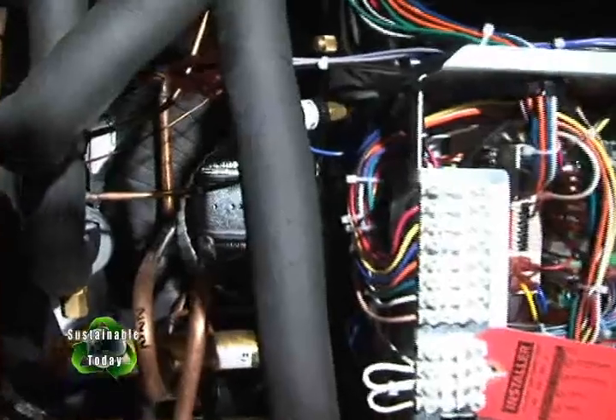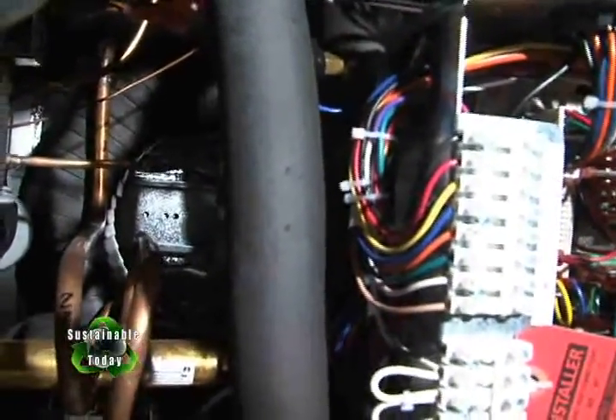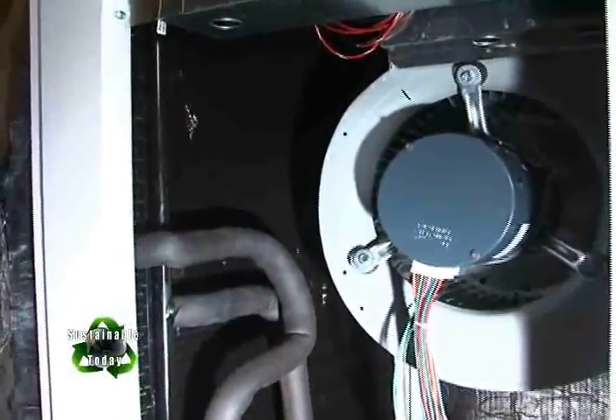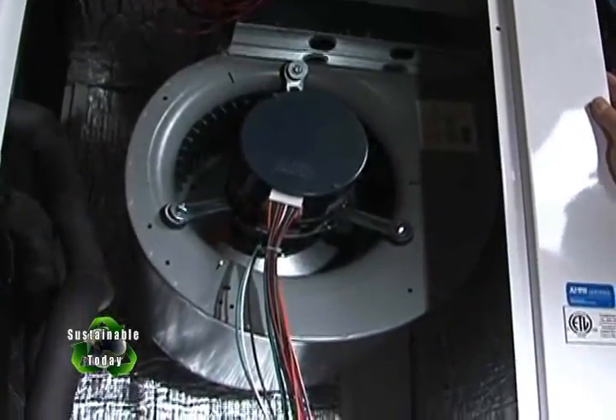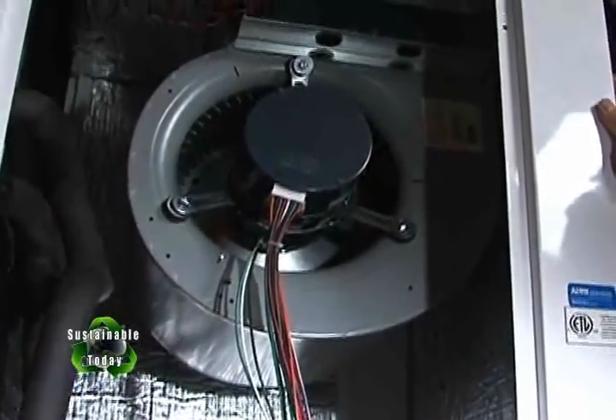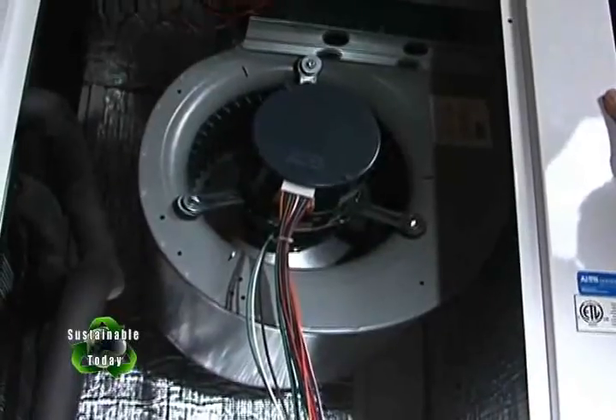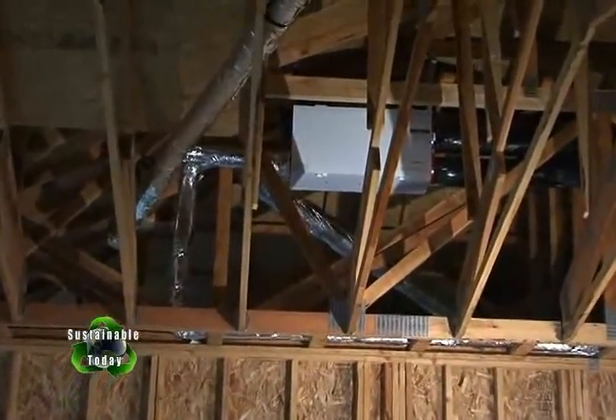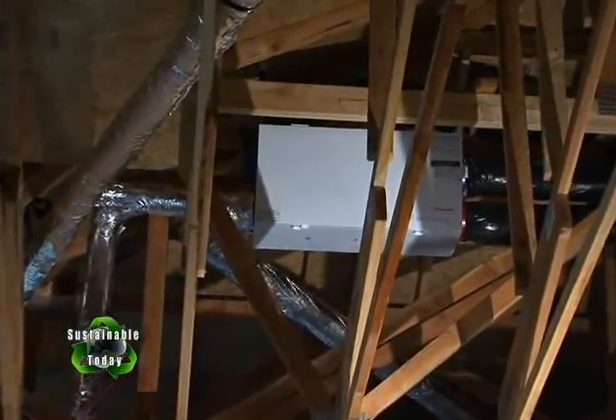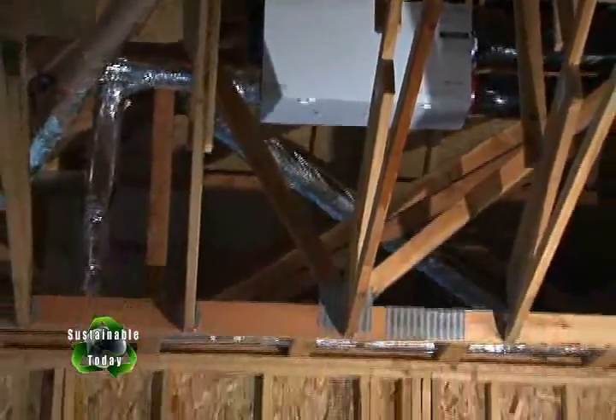This is the refrigeration coil that either heats or cools by forced air in the home. This is an electronically controlled motor that self-adjusts to the speed of the compressor. There's a microprocessor in the end of the shaft that measures what it's building — if the customer doesn't change their filter on time, it will just ramp up the speed to maintain the flow of air in the home. Here in the great room, we can look through the ceiling rafters to a white box near the roof — that's a Honeywell air-to-air heat exchanger. It takes stale air from the house, exhausts it outside, and brings fresh air in across the heat exchanger, saving 80% of the energy you'd normally waste.